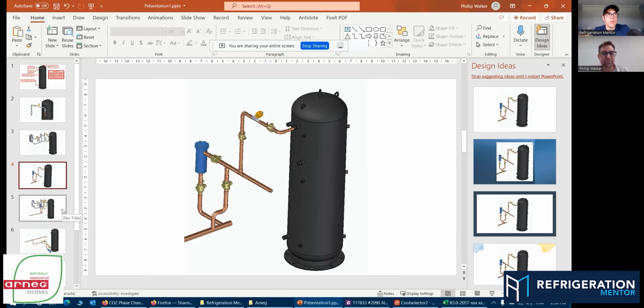Okay, that's great. So what are Arneg's rules on the type of filter that goes into the suction filter? What do you guys recommend? And is there a maintenance procedure for that? I'm assuming there is, but what filters do you use? So in terms of who we're using, in terms of manufacturing, the industry right now, in all honesty, is what can we get? So we're using a lot of the Emerson STS series, and the reason we're using that is they're rated up to 680 psi. They're readily available. We're using the Emerson cores as well. They're readily available, and you can get them off the market, really nice. We're not using anything special, guys. We also work with Sporlan, so our liquid side, the standard RC filters, nothing unusual.